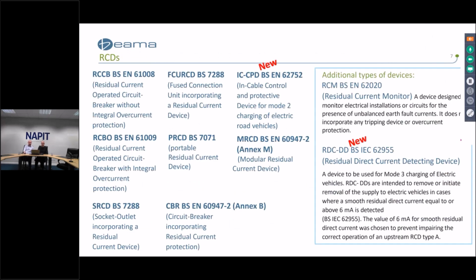Okay, so I just wanted to give you an overview of the family of products which makes up this generic term RCDs, or residual current devices, some of which you will know well, others may be lesser known and even relatively new to the market. To just run through them, we have the RCCB, or residual current operated circuit breaker without integral overcurrent protection, and the product standard is BS EN 61008. For RCBOs, that's an RCD with integral overcurrent protection, it is BS EN 61009.